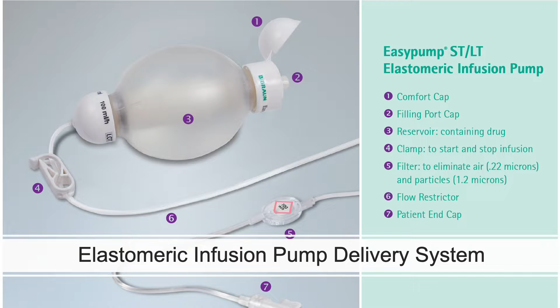Medication is delivered to the patient by positive pressure applied by the elastomeric membrane. The flow rate is determined by the combination of the flow regulation device or flow restrictor and the positive pressure of the elastomeric membrane. This pressure delivers the solution against the back pressure of catheters and blood pressure of the patient's veins.